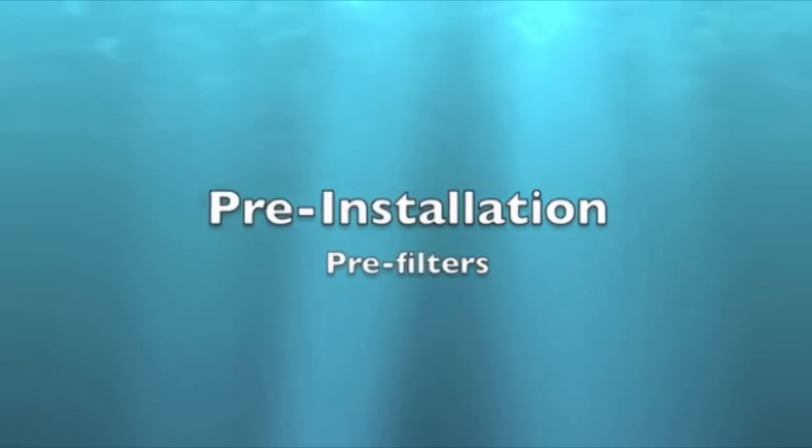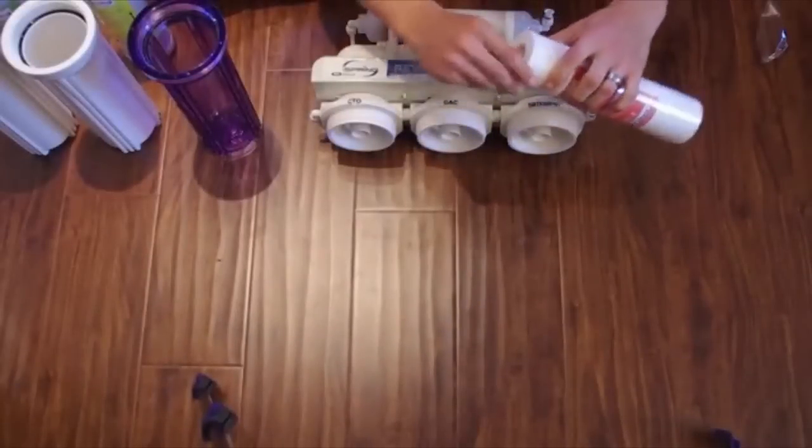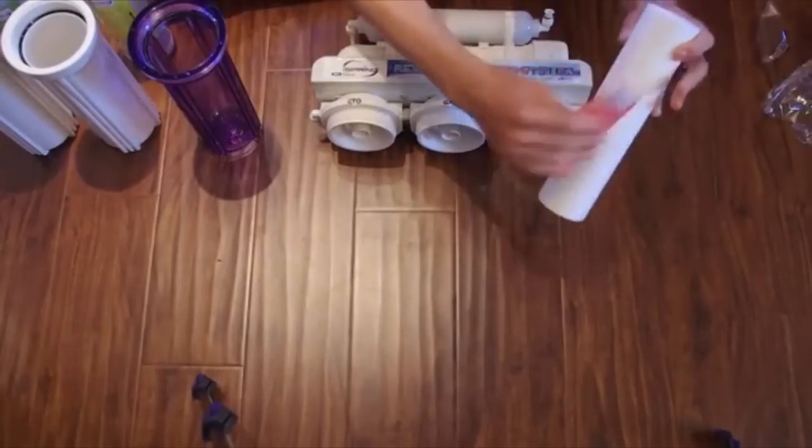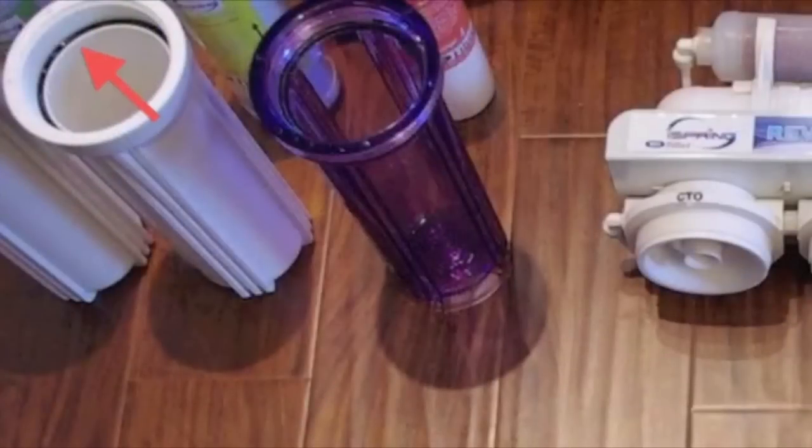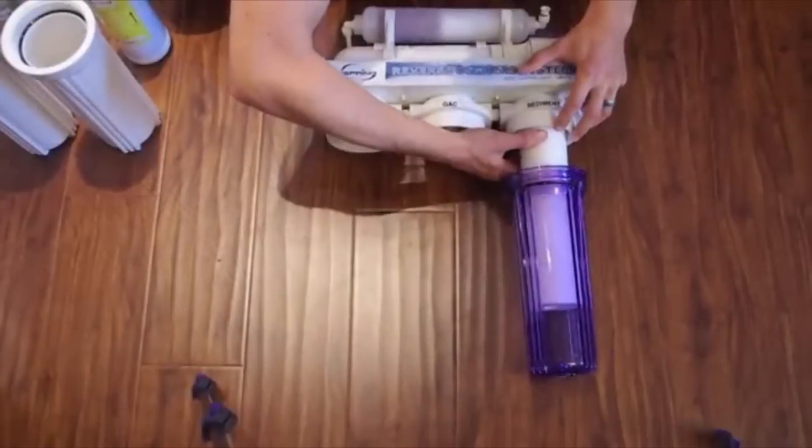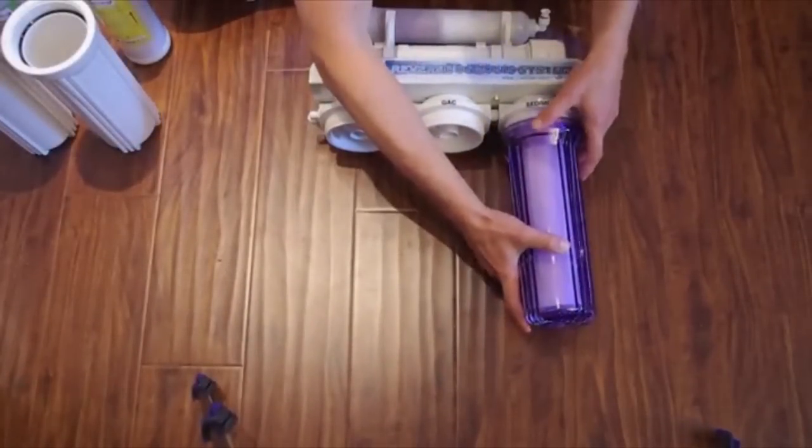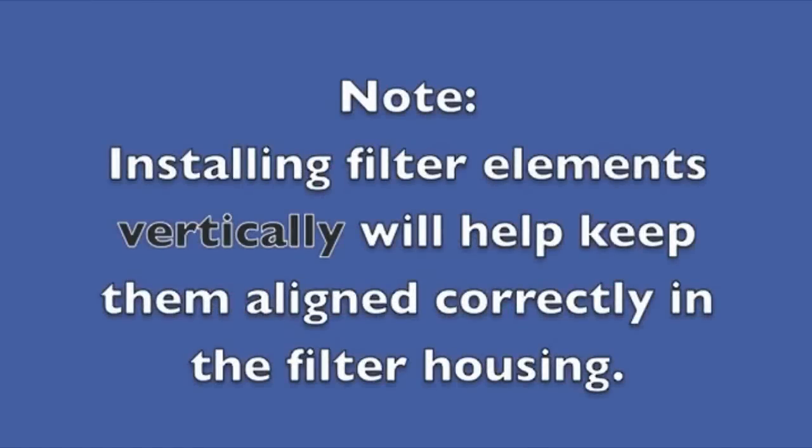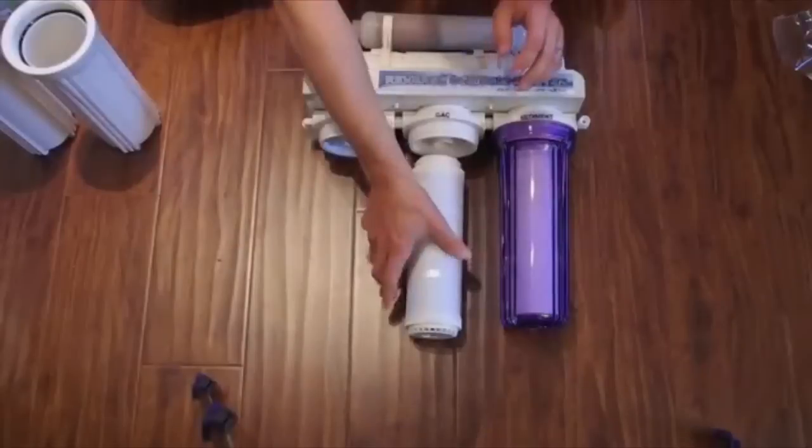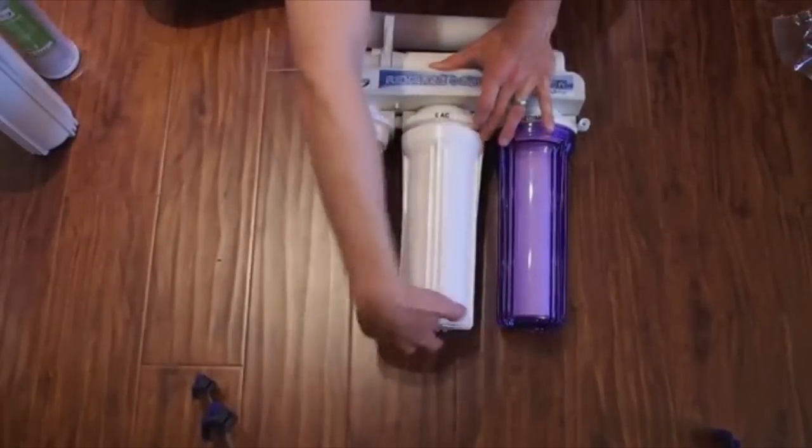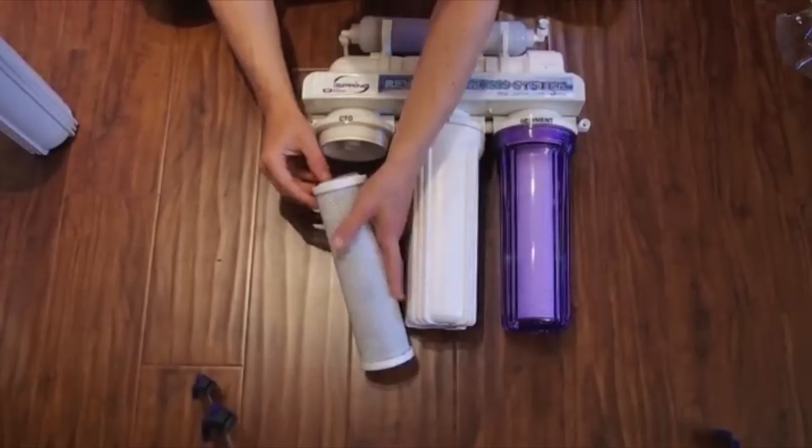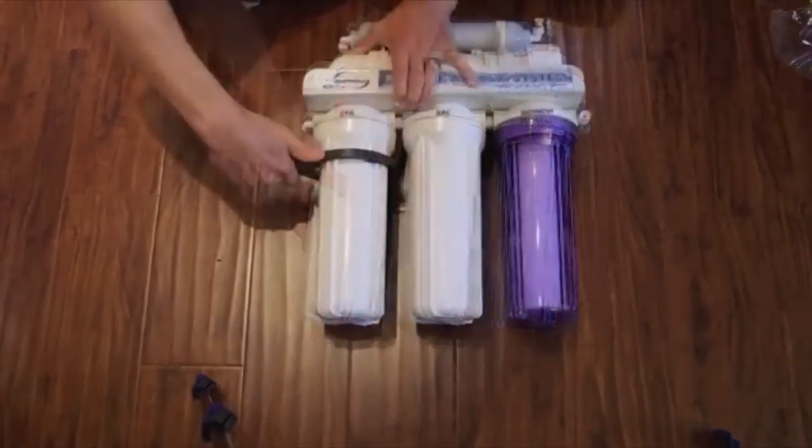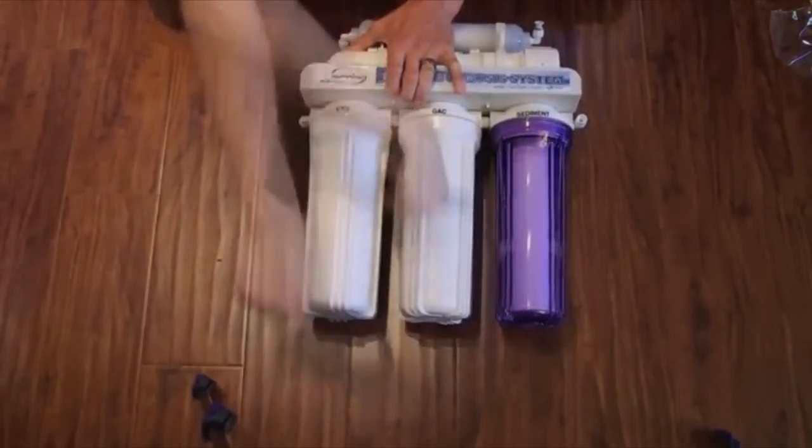Install pre-filters. Remove the protective wrap from each filter before installing. Make sure the O-ring is seated in the top of the housing. Install the filter in the housing and then carefully screw the housing onto the filtration system. Installing filter elements vertically will help keep them aligned correctly in the filter housing. Repeat the process for the two remaining filter elements, making sure to match them to the correct location. Tighten each filter housing using the supplied wrench.